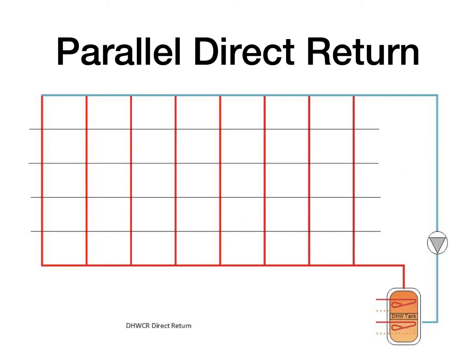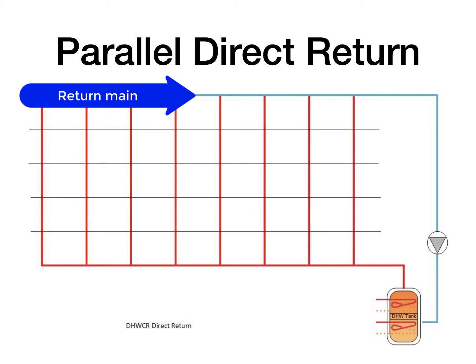Now showing is a parallel direct return domestic hot water supply and recirculation return system. As you can see, the supply and the return go in opposite directions to each other, hence the direct return method. Each one of the horizontal lines indicates a floor. The vertical red lines would be the hot water mains that start out from the bottom floor and typically reduce in size as they drop branches, headed for the very top. At the very top of the system is the beginning of the circulation return lines.